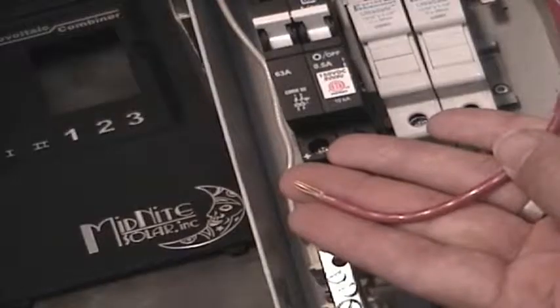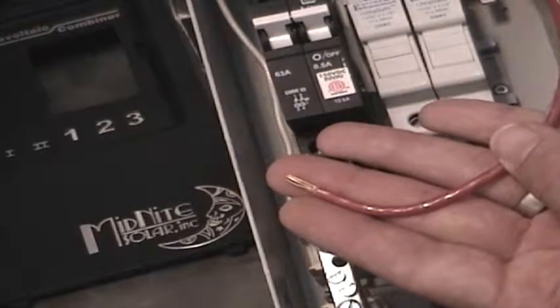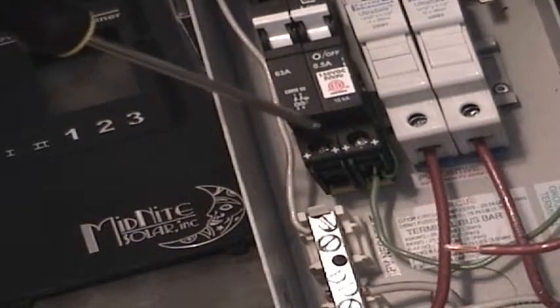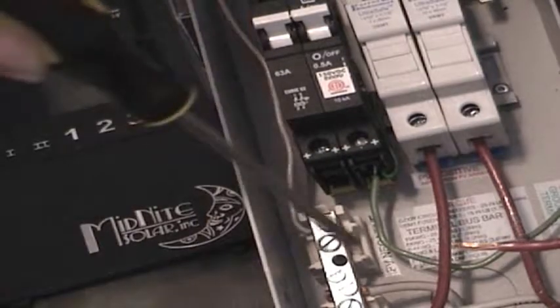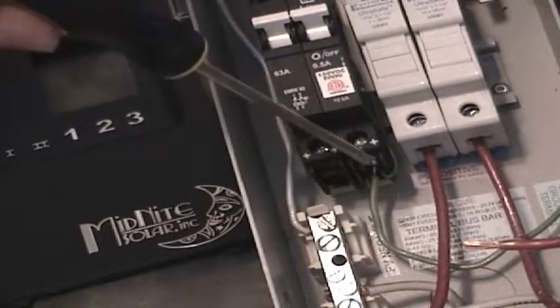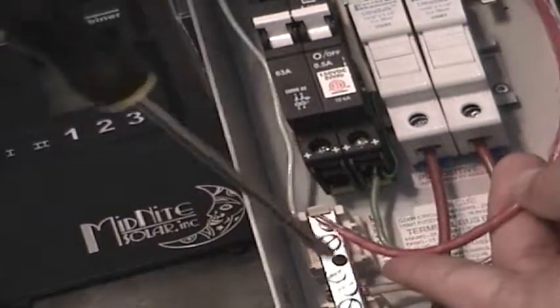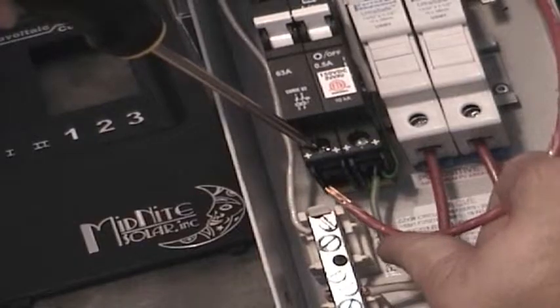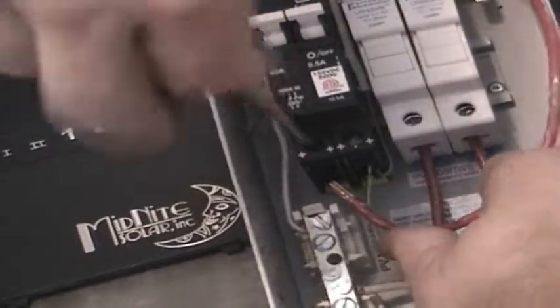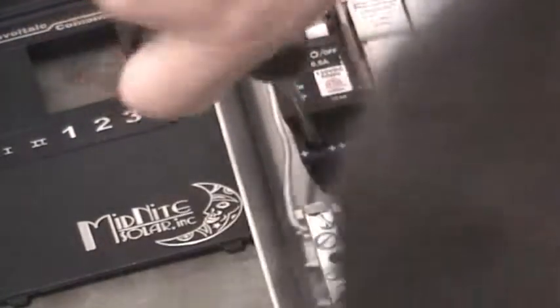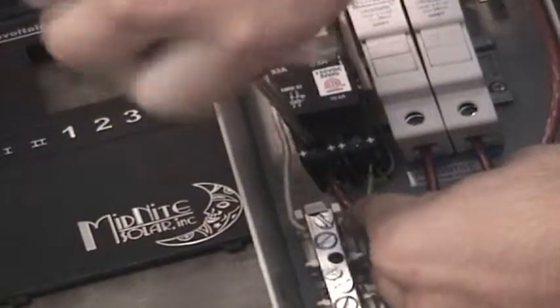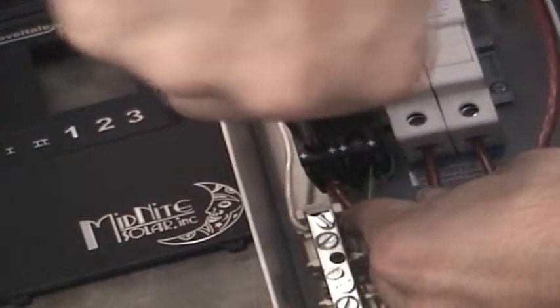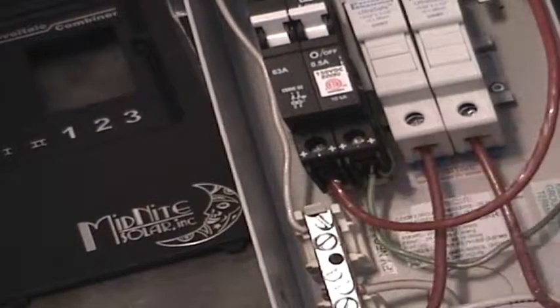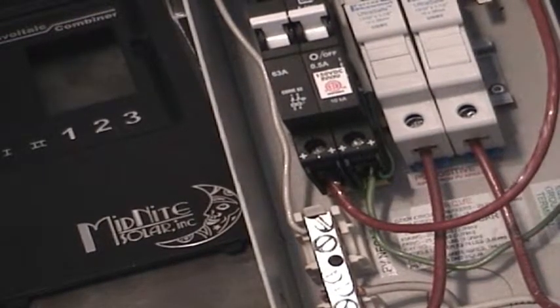Okay. Now let's take the other end of our red 1-foot 10 gauge piece of wire. Let's connect it to the bottom of our GFP device. Notice again that the green ground wire is connected to one side of the GFP device. So let's connect our red wire to the other side of the GFP device. We will loosen the screw, then insert our cable, tighten up the screw, make sure there's no bare wire sticking out, tighten it up good and tight, and now our combiner box is ready to be installed with our solar panels.